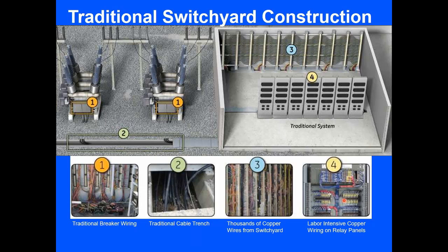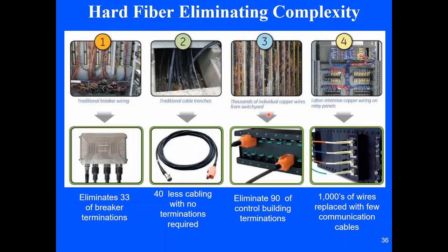One great example of fiber is I can run all those right in the switchgear to what's called a hard brick. This uses a connector that uses a process bus called IEC 61850 process bus. Now I just run one fiber connection. In this case, we actually run 4 identical fibers back through this cable. And I can eliminate about 33 connections there.